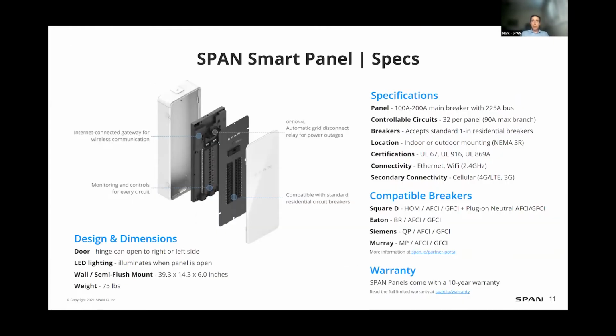This is to walk you through all the specifications. Think of SPAN as a traditional solar-ready panel. We have a 225 amp bus bar, basically a 200 amp rated panel. You can derate it, put it at 100 amp or less, and use it for different applications, but it comes standard as 200.